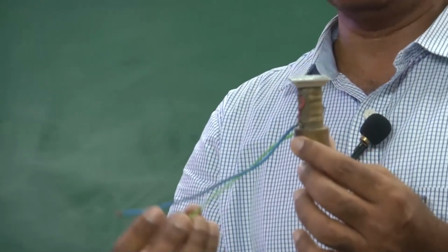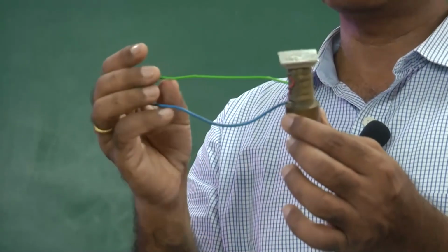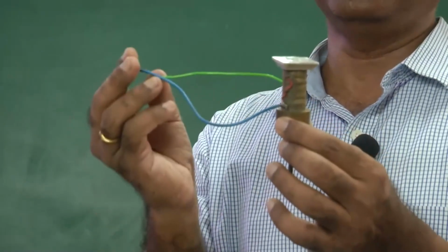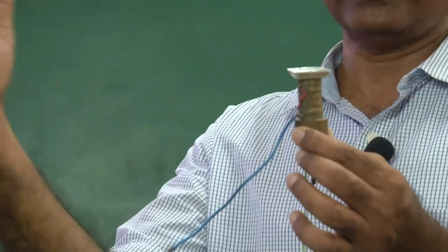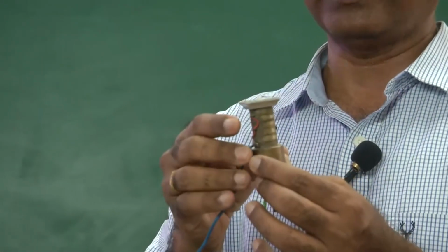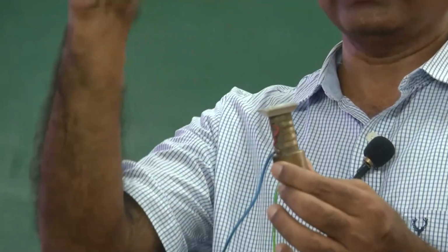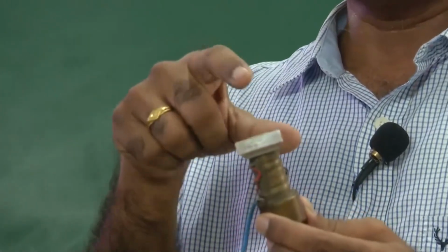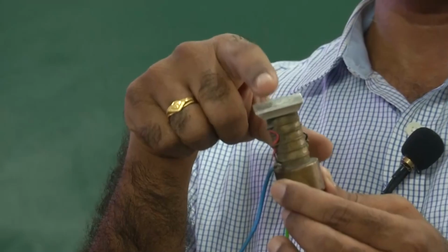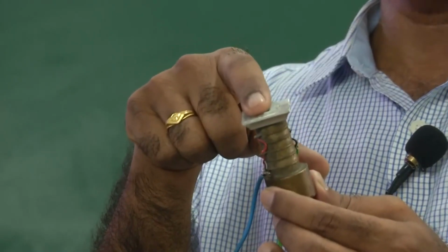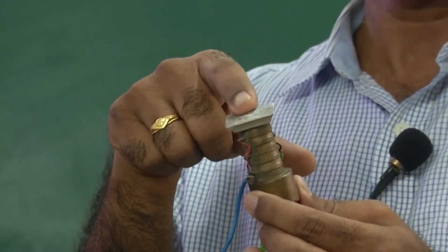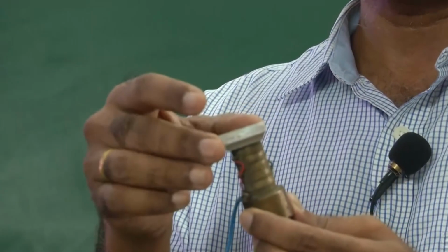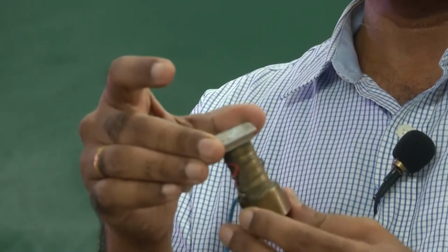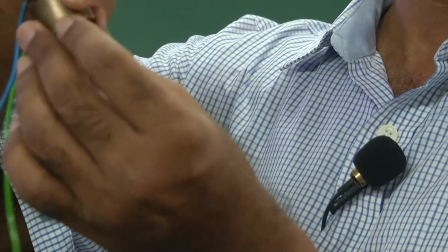So, what we are going to do, for finding out the natural frequency of this entire sensor unit, is feed it with a signal whose frequency we are going to scan over a large frequency band and check where the amplitudes of vibration increase. Now, we are going to put a sensor at the top face of this transducer, and we will keep on recording or tracking the vibration amplitude as the frequency is swept across a reasonable frequency range. Now, the sensor itself is a vibratory system. So, what you notice here is there is a metallic block at this point.